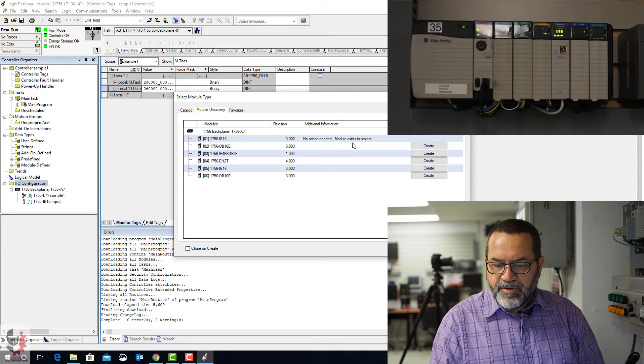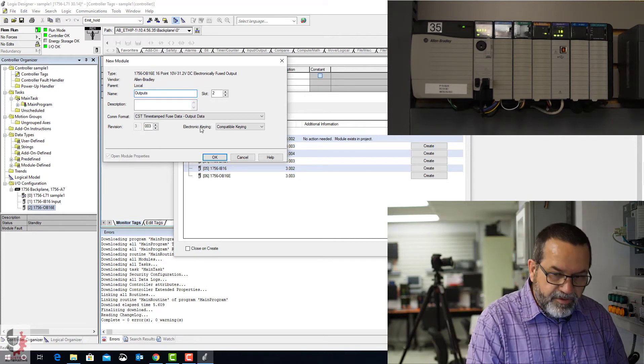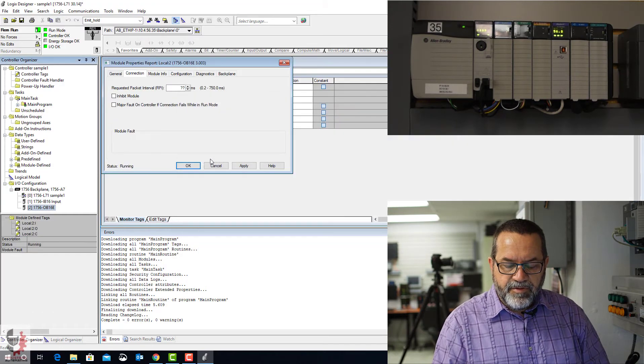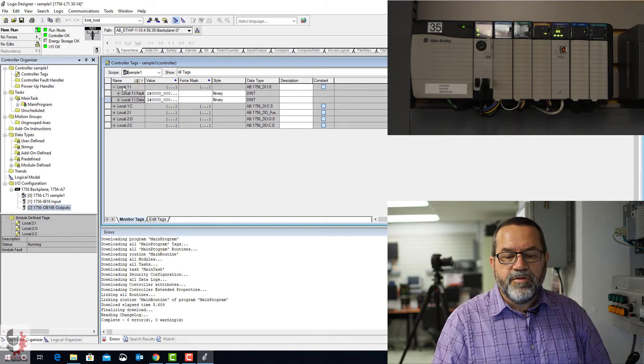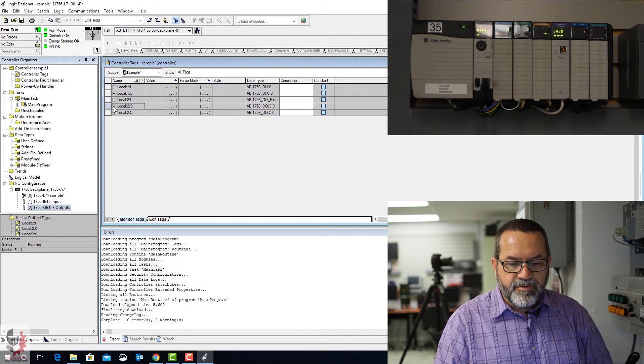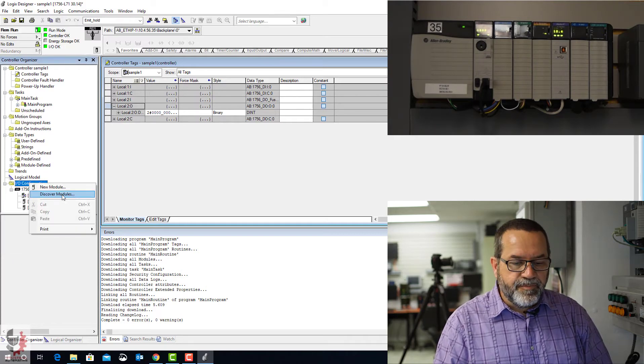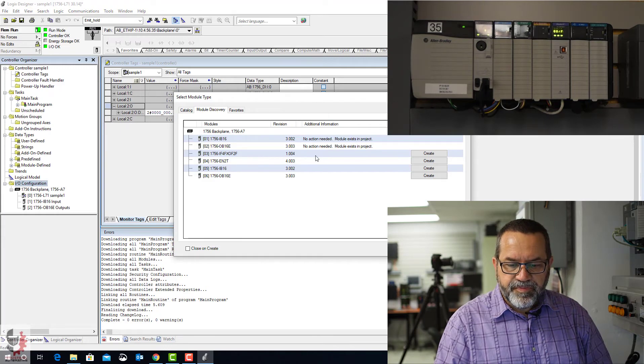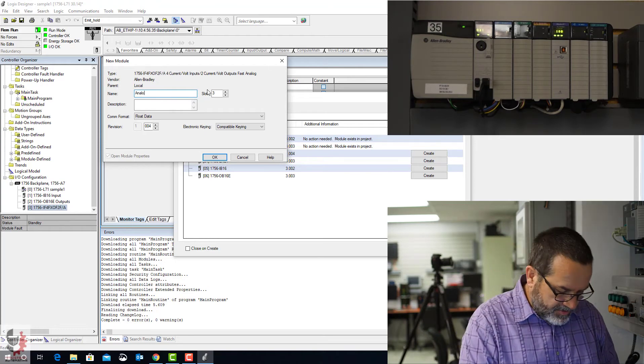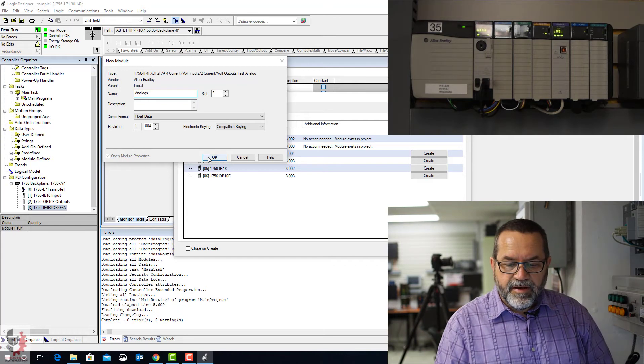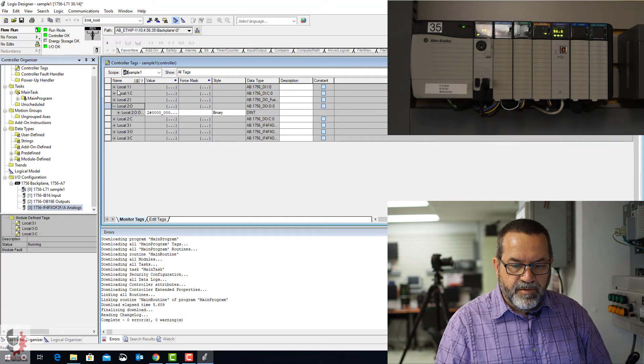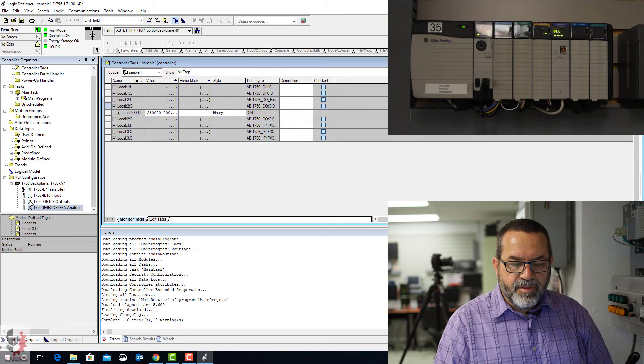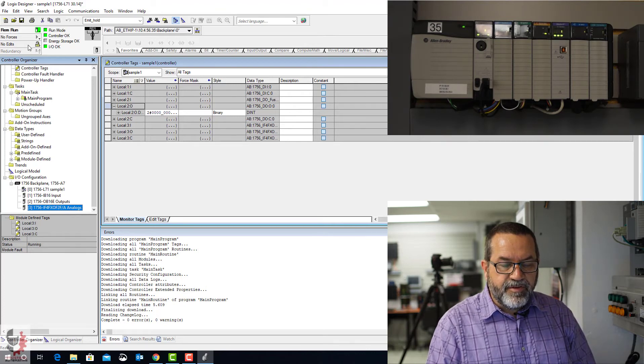Notice that first one, no action needed, module exists. I'm going to create the second one. That's my outputs. Hit OK a few times. And now in my controller tags, I'm showing local, one, inputs. And here's my local, two. There's my outputs. I'm just going to do one more module. So right-click on configuration, discover. Now I'll do this third one. And that's my analogs. Okay, so I've got local one, two, and three in my tags. Down here, it shows my modules. There's my inputs, my outputs, and my analogs.